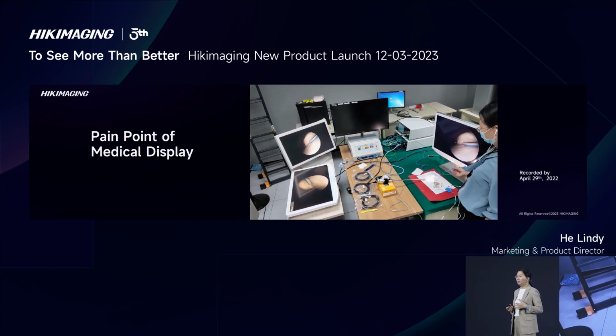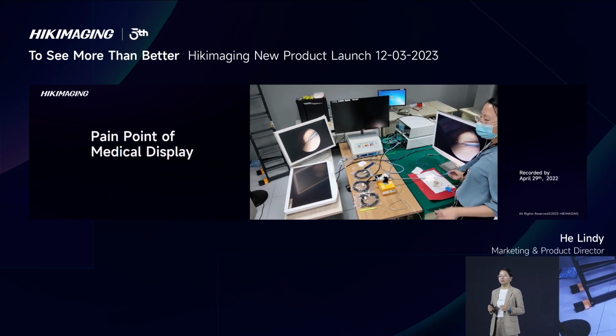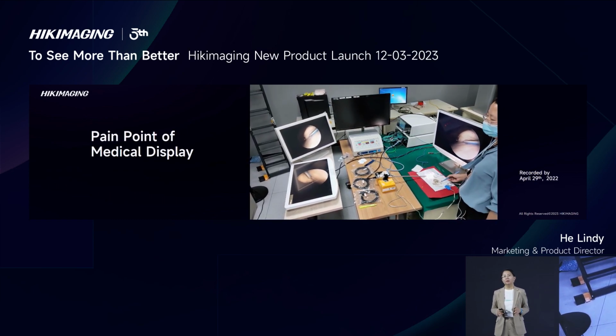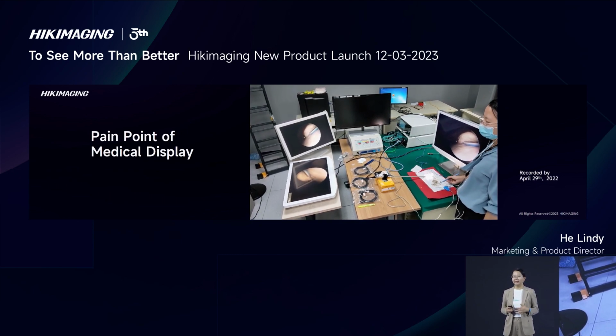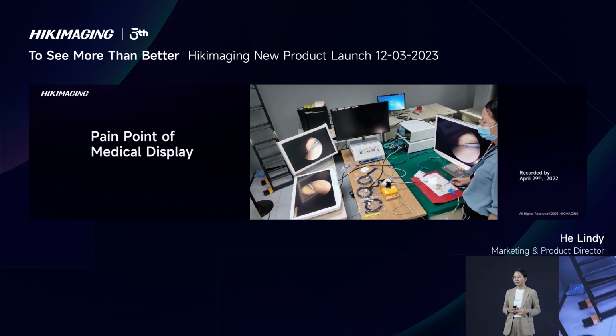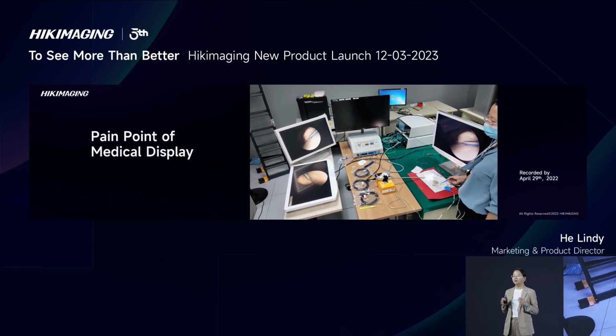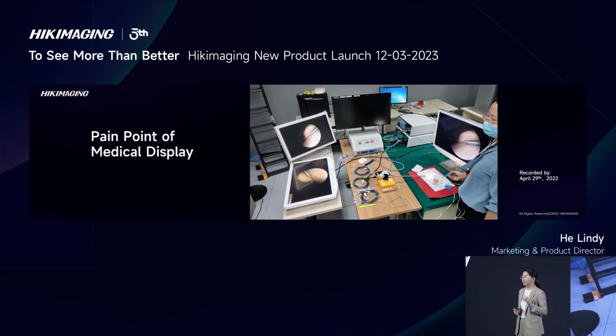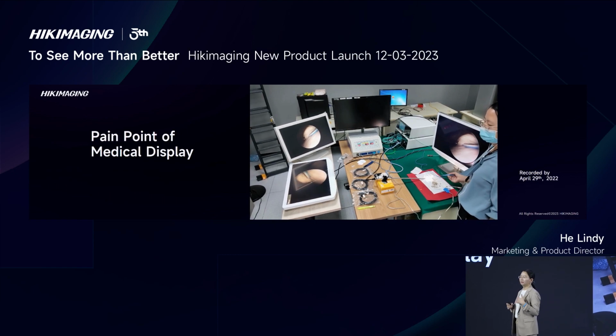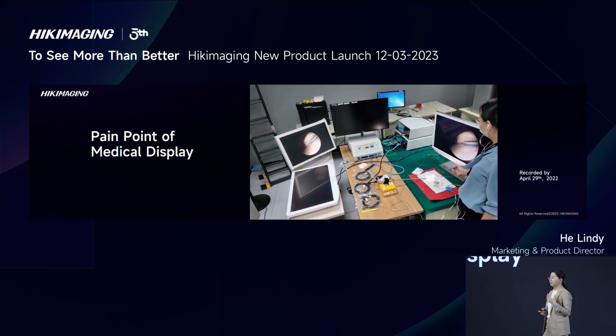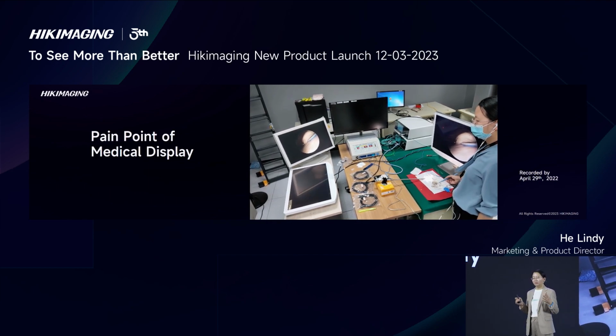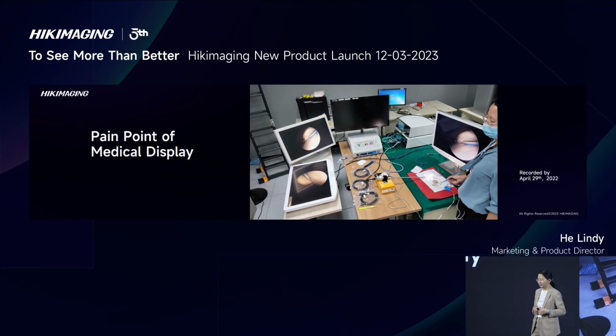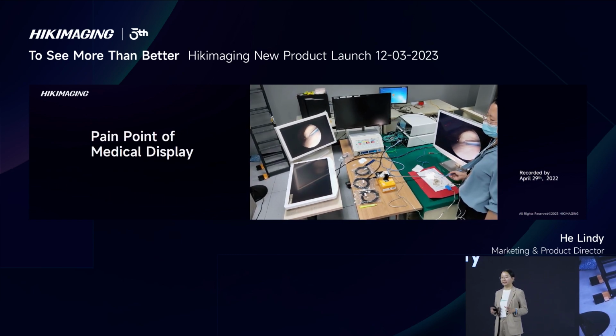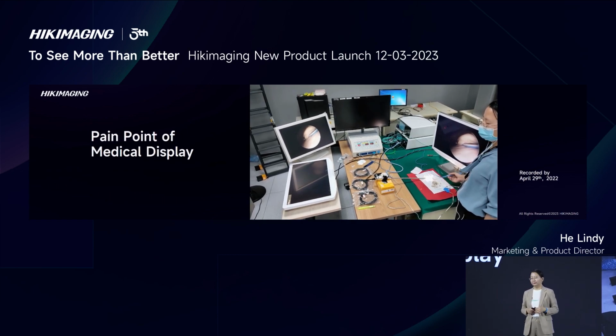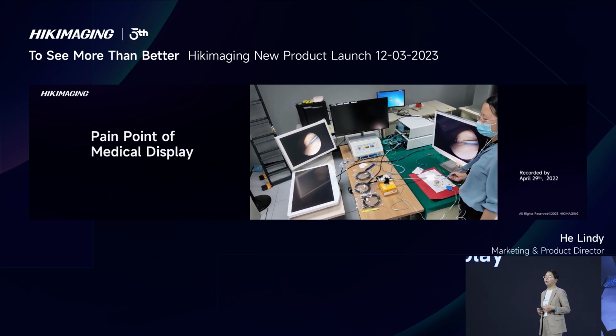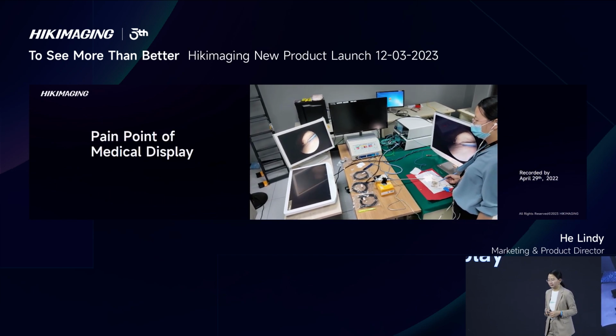At the beginning of our business, we didn't want to make a surgical monitor. However, we found more and more complaints caused not by the endoscope system, but by the monitor. We did a lot of investigation and found that the monitor's reliability is not that good. There are no regulatory requirements for the monitor. As it's not a medical device, most manufacturers did less EMC protection design. When the whole system works together under surgical electrosurgery conditions, the monitor loses signal or flickers as interference occurs.